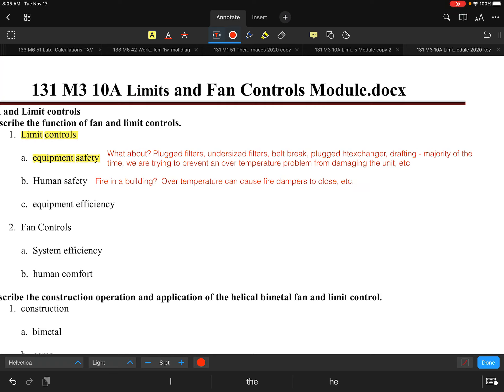From a human safety standpoint, any unit burning fuel or using electric heat — without limits — could overheat and either burn up equipment or start a fire. This is also why you should never jump a limit out on a permanent basis. If a limit is tripping, it's clearly telling you something is wrong, and that needs to be addressed.